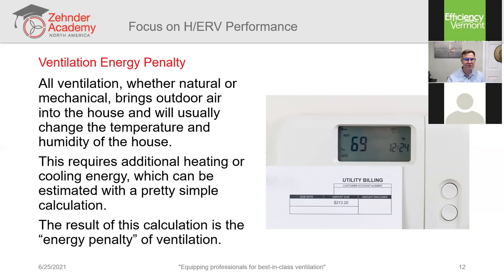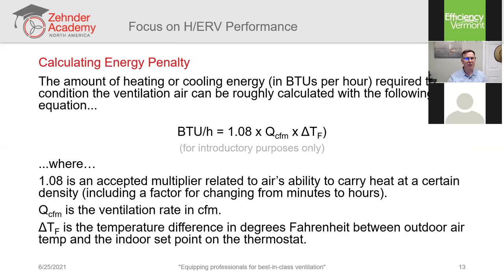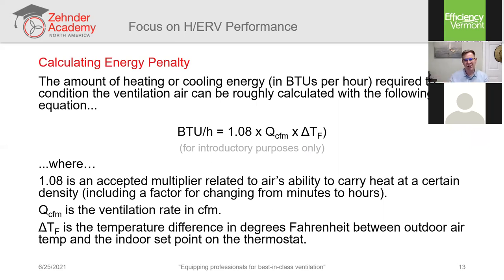We can estimate this cost — it's called the energy penalty of ventilation or thermal/ventilation losses. The formula is: BTUs per hour = 1.08 × CFM × ΔT (in Fahrenheit). The 1.08 factor incorporates the specific heat capacity of air and converts CFM to an hourly rate. CFM is the ventilation rate, and ΔT is the temperature difference between outdoor air temperature and the indoor thermostat set point.